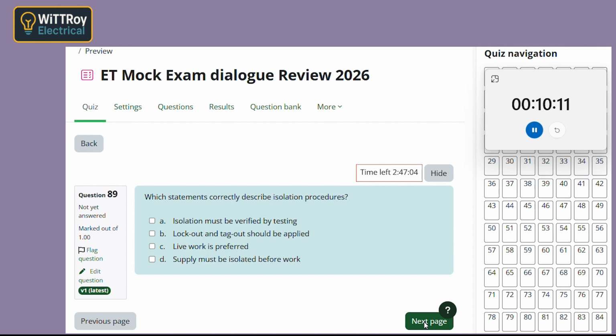Question 89. Which statements correctly describe safe isolation procedures? Isolate, test, and lock and tag? Yes, that's the full process. So why all 3 steps though? Well, isolating removes the supply, testing confirms it's actually dead, locking and tagging stops someone else from turning it back on. So each step covers a different risk. Exactly. If you skip one, there's a gap. So live work isn't the normal approach. No, isolation is always the safer option.